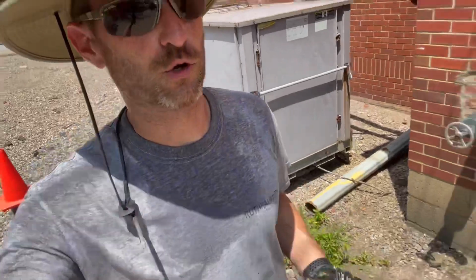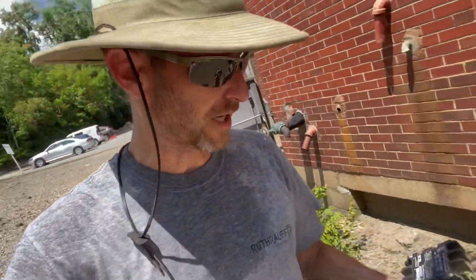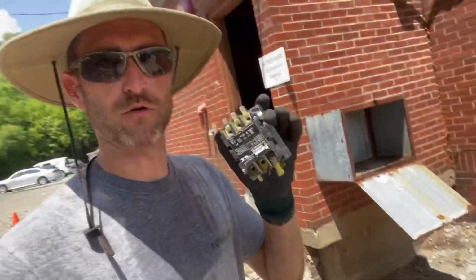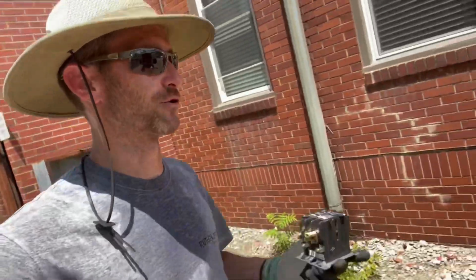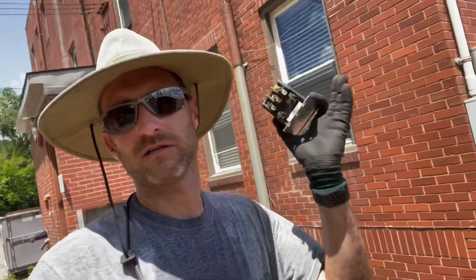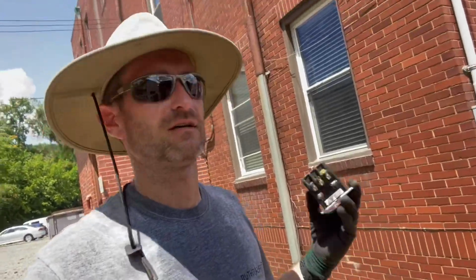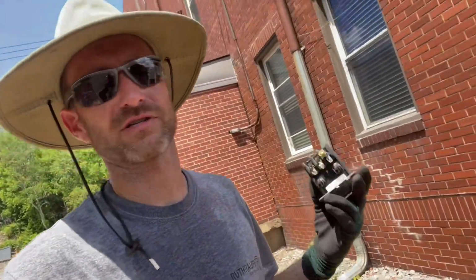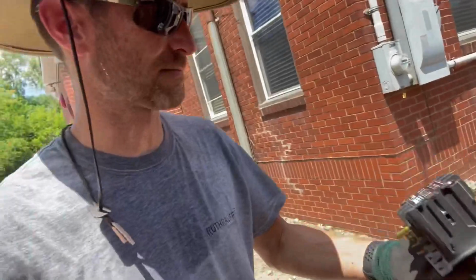Okay, while that's cooling, I had to clean up. Change the contactor too. Always change a contactor when you change motors. Say that motor costs $1,000. This contactor might be under $100. Who knows? I can't give the exact amount on that, but you change it, just like you put new tires on your vehicle, get the alignment, okay? So. All right, guys, you know what?